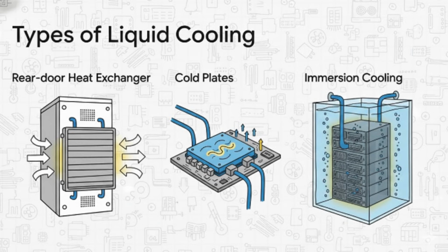You have things like a rear door heat exchanger, which is basically like putting a car's radiator on the back of the server rack. You can take it a step further with cold plates, which attach a liquid-filled block directly onto the hottest parts, like the CPU. And then you have immersion cooling, the ultimate solution, where you literally submerge the entire server into a tank of non-conductive fluid.